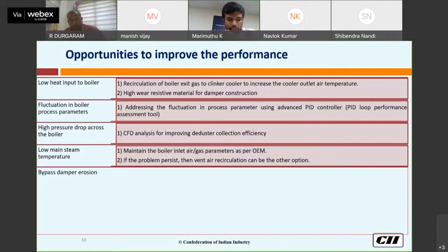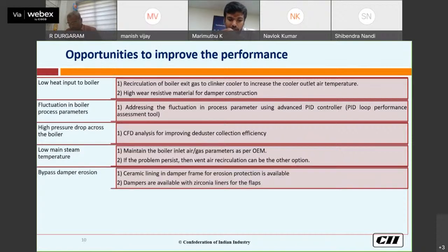The next one, bypass damper erosion. Nowadays ceramic lining in the damper frame for erosion protection is available, so we can go for that. And dampers are also available with zirconia liners for the flaps.